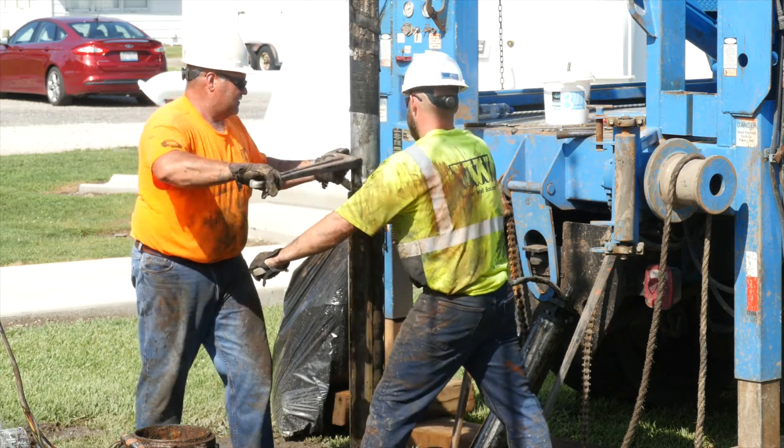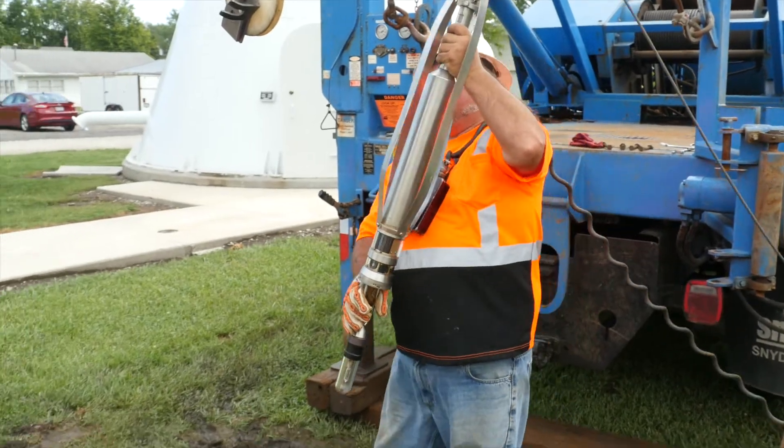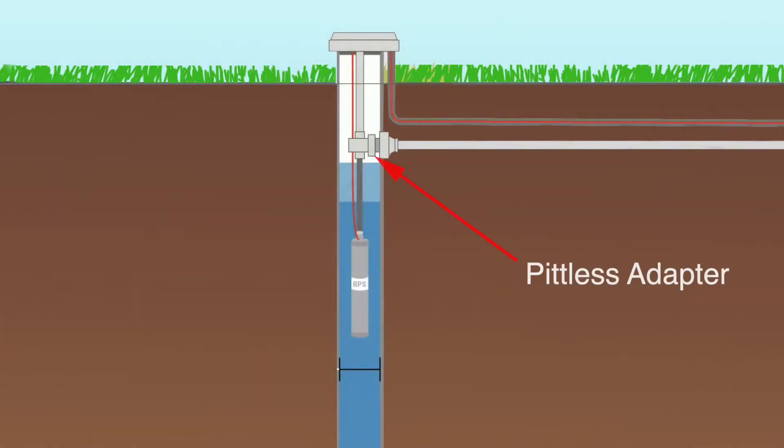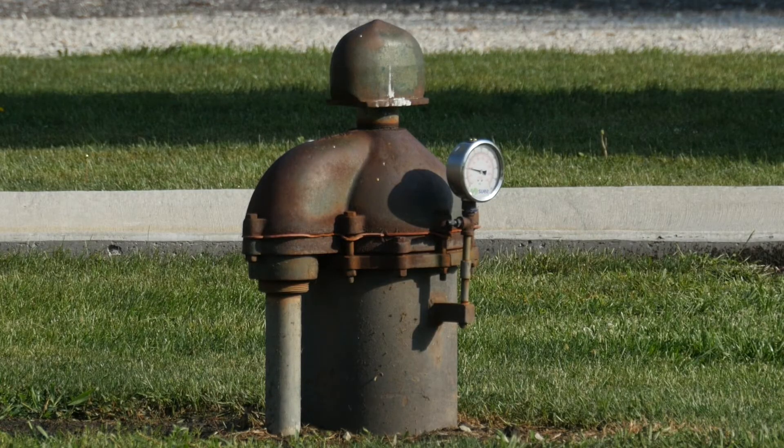They've identified the source — the pitless adapter was leaking, bringing in water from outside, causing the corrosion and tuberculation, which harbors bacteria. So they're going to clean off the tuberculation, disinfect, and install a new pitless adapter that is en route to the job site. That well is an asset to the community which they have to maintain, because the EPA won't allow them to use that well unless the bacteria is gone. They have to invest money into that well to bring it up to EPA standards. For more information on RCAP training materials, go to RCAP.org.